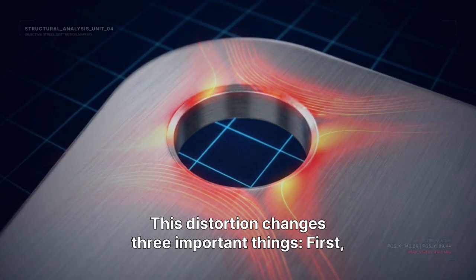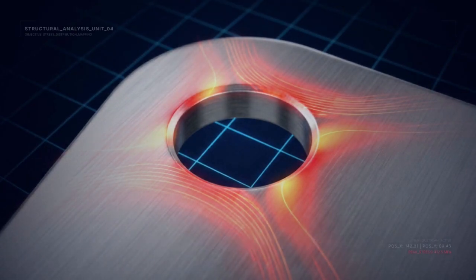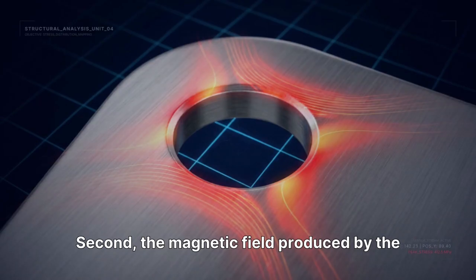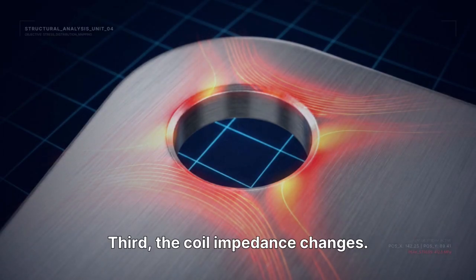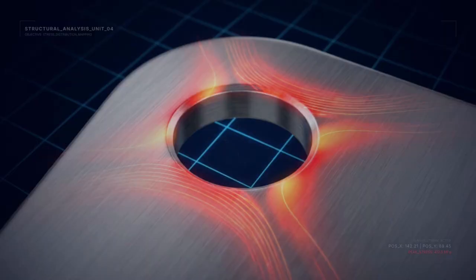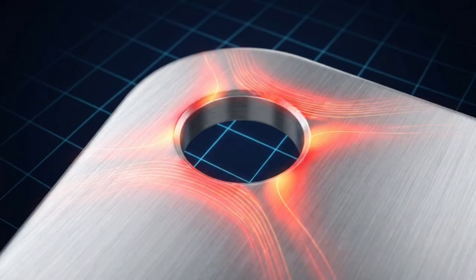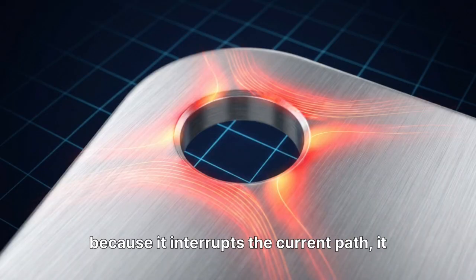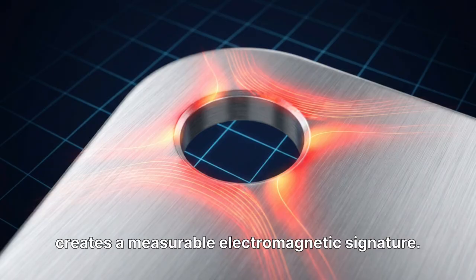This distortion changes three important things. First, the current density changes. Second, the magnetic field produced by the eddy currents changes. Third, the coil impedance changes. This is detected by the instrument. The crack may be very small, but because it interrupts the current path, it creates a measurable electromagnetic signature.